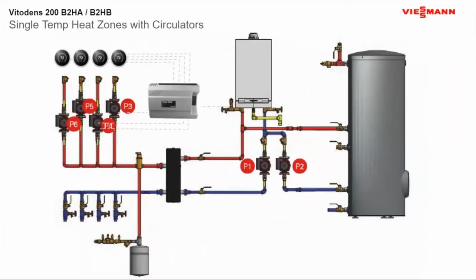Now this one's just showing you a different zone control using pumps. Same thing, you're going to send just the end switch over to the boiler to DE1 or DE2, whatever one. The prior picture was a Taco. This one here, you could have 2 of these in there and have 2 different end switches controlling these systems. It's always going to go to the hottest temperatures first if you're looking to know that. So hopefully if you're doing any type of mixing, like for radiant, you're going to have some type of mixing valve as well.